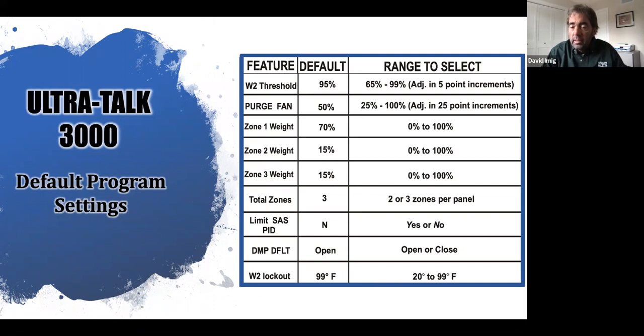In this particular case, no means I want to use my PID loop. I do not want to limit it. If I select yes, I take PID out of the equation. The PID, in another sense, is the algorithm formula to all this operation. I'm selecting no because I want to use the feature that is available to me to help this operate and satisfy calls. Then damper default: when this system is sitting idle, is my damper closed or open?